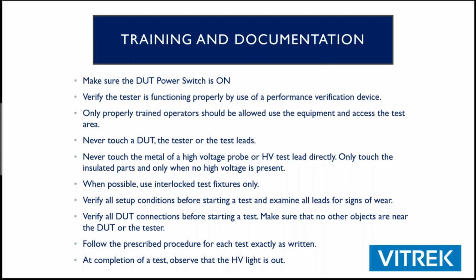So you definitely only want properly trained operators in the area. Usually when there's issues, it's people that might be walking by, touching things, kind of curious, and are not the operators that are using the units on a daily basis. Never touch the device or the test leads during the test. It's an unnecessary risk. Use an enclosure where it's possible. Be consistent in your test setup and your conditions, things like that. We'll leave this list here for you if you want to reference it later, and we will be emailing out this PowerPoint.